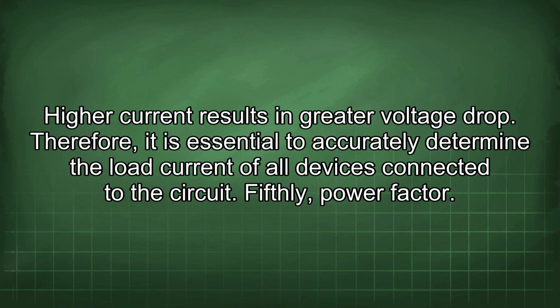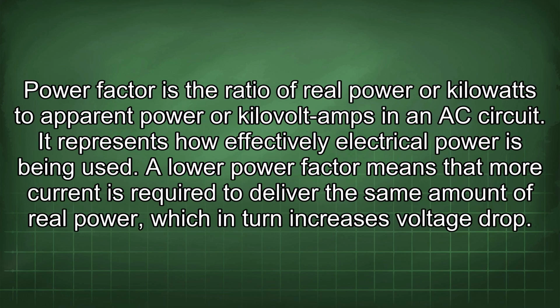Fifthly, power factor. Power factor is the ratio of real power, or kilowatts, to apparent power, or kilovolt-amps, in an AC circuit. It represents how effectively electrical power is being used. A lower power factor means that more current is required to deliver the same amount of real power, which in turn increases voltage drop.